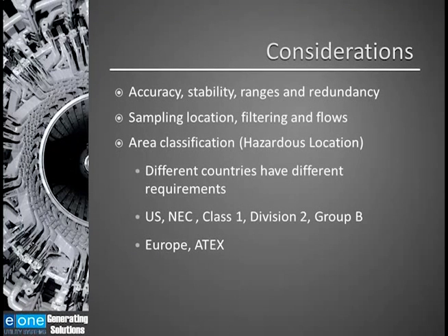These are some considerations when speccing out an analyzer. Certainly you want the analyzer to be accurate. I believe as important, you want it to be stable. You don't want to keep calibrating this piece of equipment. You'd like to have a piece of equipment that would go a minimum of 6 months without having to be recalibrated. You want the ranges to be such that they'll cover all of your applications.